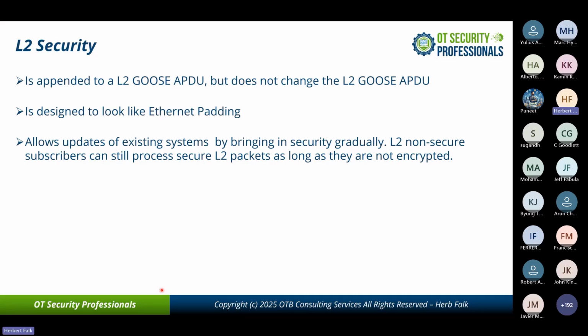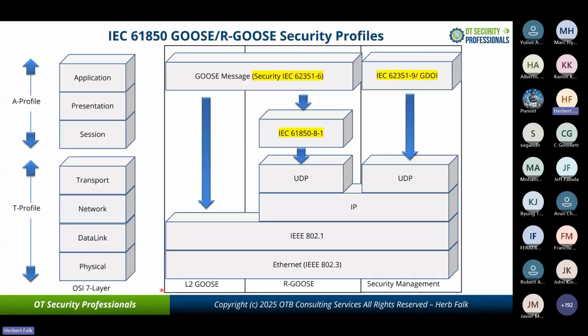And then you can update those subscribers individually, but you don't require a bulk update of your system just because you're bringing in layer 2 GOOSE or sample value security. So one of the things that's in OT's best interest is to always provide a migration strategy so that you don't have to do a bulk replacement. We really do try and design that in up front, and we've been successful with GOOSE, R-GOOSE, RSV, and sample values here.